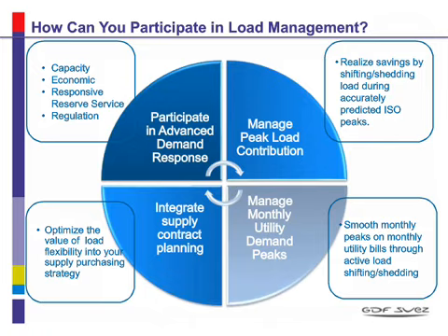On the upper right-hand side, we can begin to talk about a different set of opportunities related to managing your peak demand. Many of the pass-throughs that you see on your energy bills coming from utilities and suppliers are based on charges that relate to your peak usage. At the transmission level, or the ISO level, those charges are often calculated based on how much load you're consuming during a very specific hour at which the system-wide load peaks. So if your load is climbing and helping drive that system load to its peak, you're going to be charged for the rest of the year based on how much you were using during that particular hour.